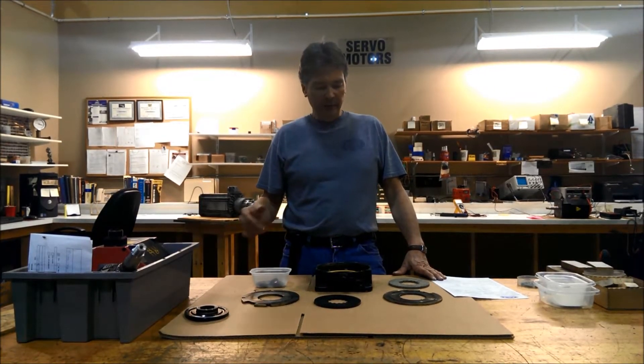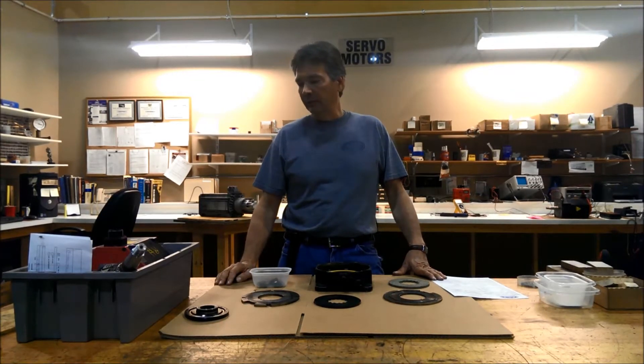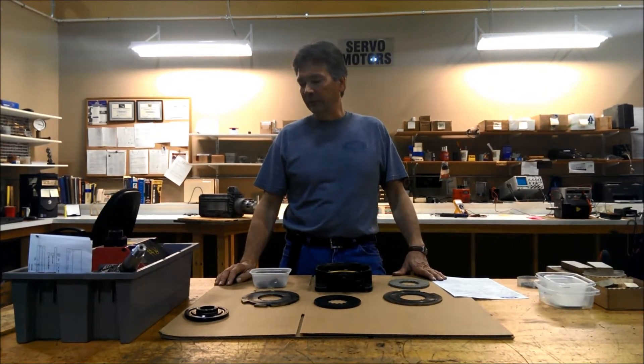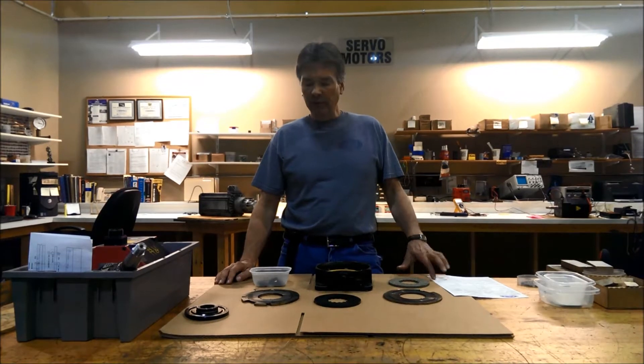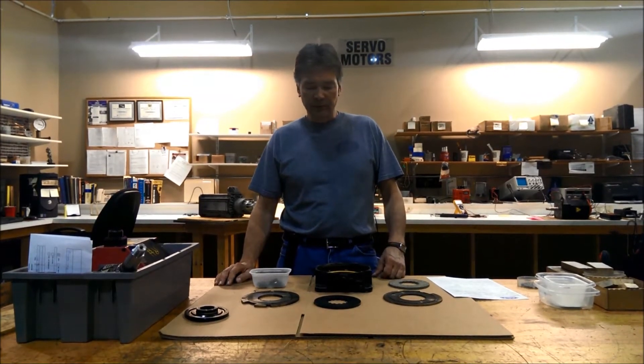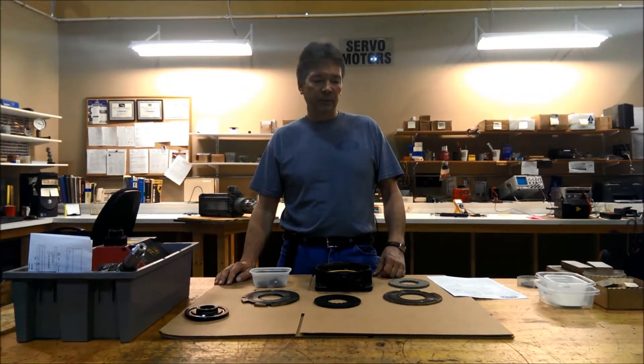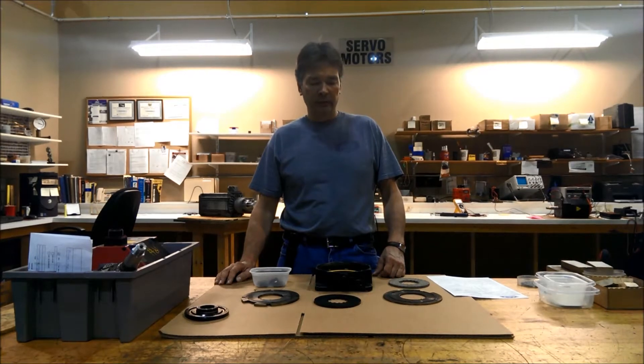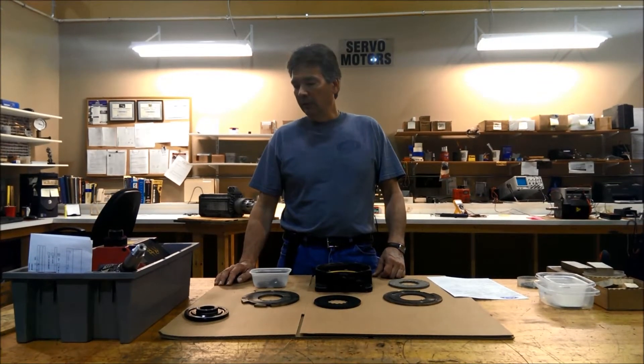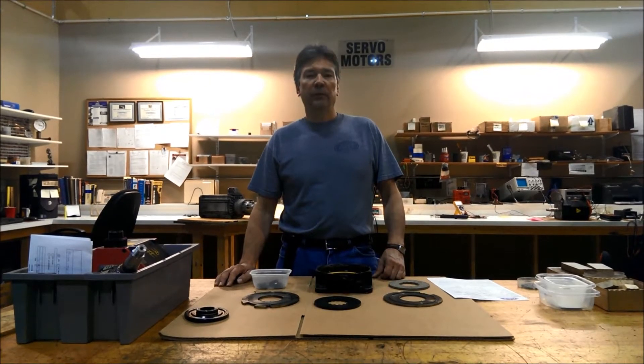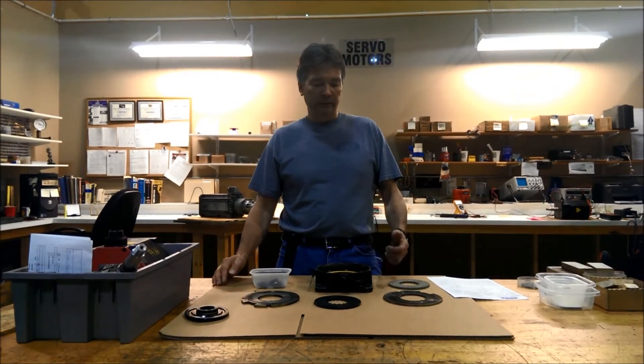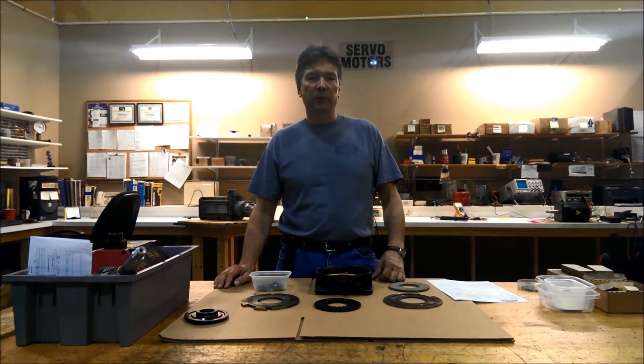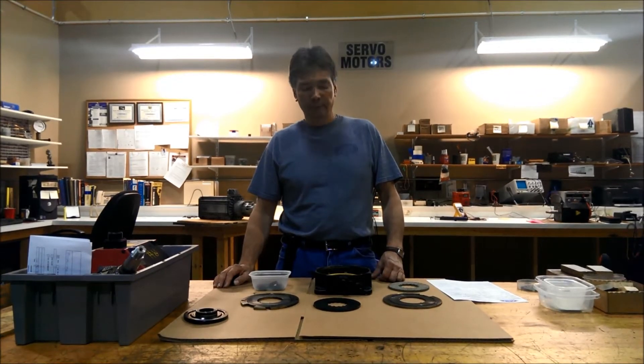What we have here is a FANUC motor that's in various stages of disassembly. One of the things I wanted to talk about quickly was the brake assembly because this seems to be a common problem with FANUCs. What happens is the brake assembly gets saturated with grease and as a result the brake assembly won't work anymore and it causes collision faults.